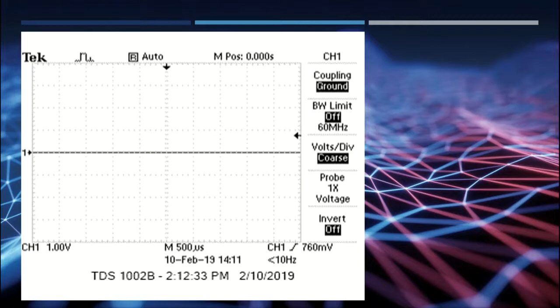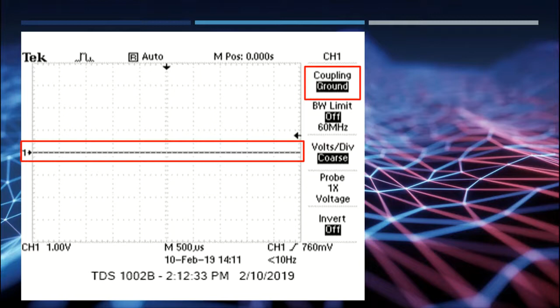Now, just in case it's a little bit tough to see, I'm going to show you what it looks like by capturing the screen. Alright, so I went ahead and captured what was on the screen a minute ago. If you look on here, you'll notice that the coupling for channel 1 now says ground, and the signal is just a straight line that goes across the screen. So again, this is how you would do coupling on this oscilloscope, and this is what you should expect on your oscilloscope when you figure out where your coupling buttons are. All you have to do is hit the ground or position it to ground, and you should see approximately the same thing on your screen.